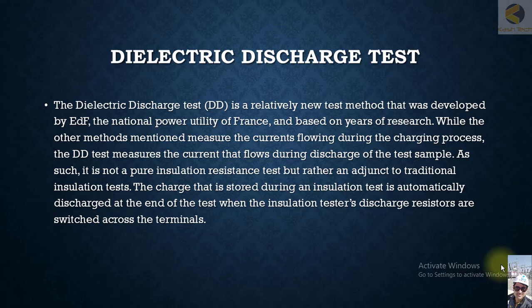While other methods measure the current flowing during the charging process, the Dielectric Discharge Test measures the current flow during discharge of the test sample. As such, it is not a pure insulation resistance but rather an adjunct to a traditional insulation test. The charge stored during the insulation test is automatically discharged at the end of the test when the discharge resistors are switched across the terminals.